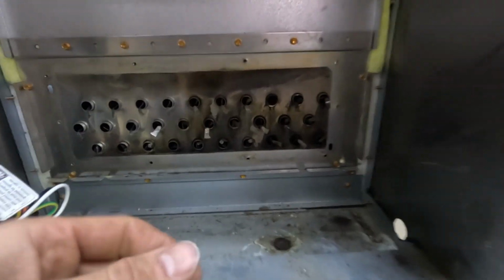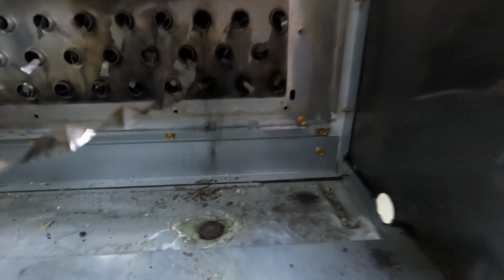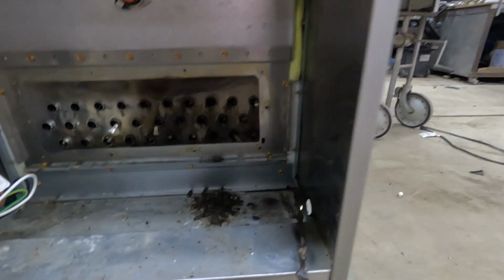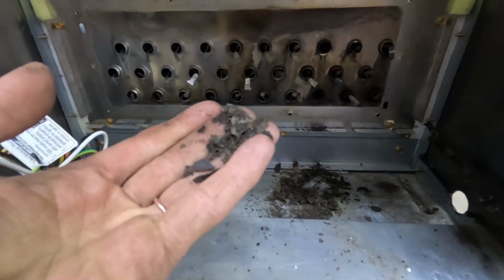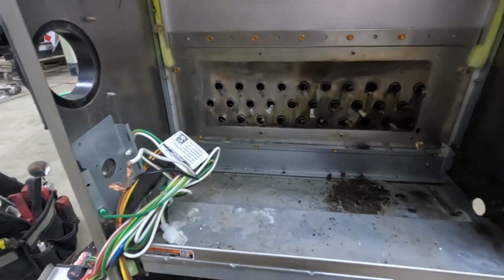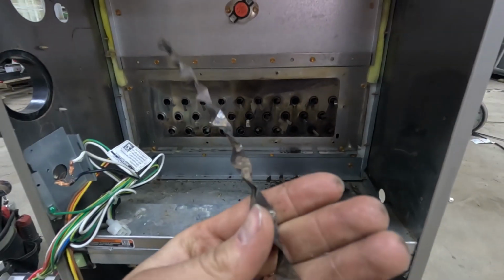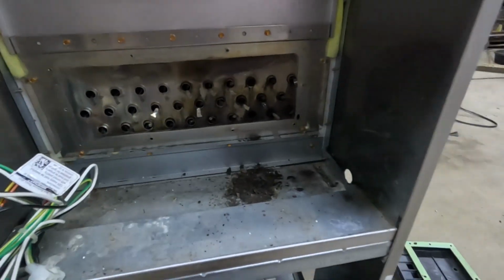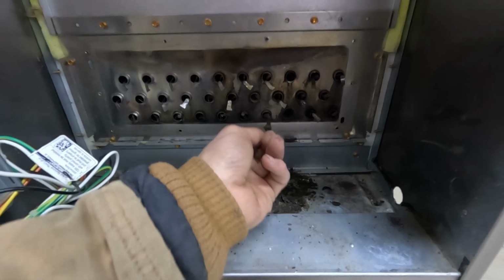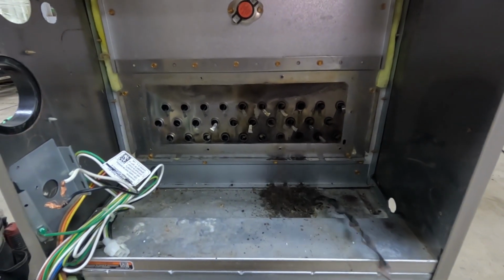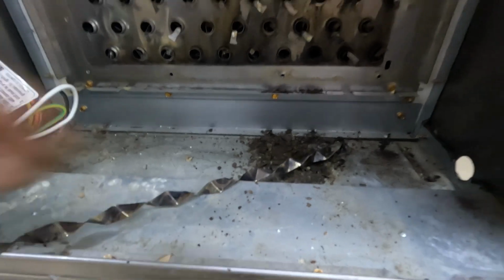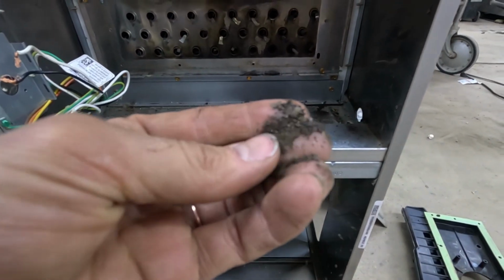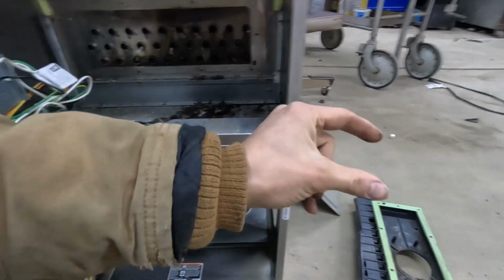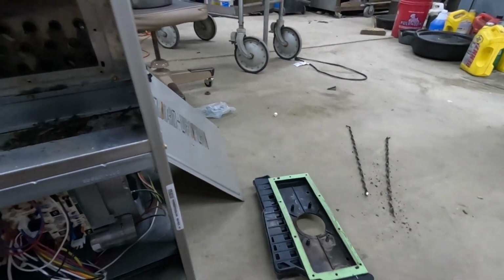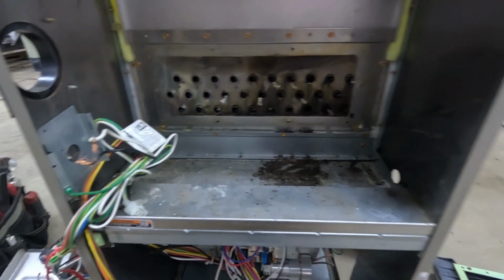There's our actual secondary heat exchanger. And you can see it does have a bunch of debris clogging it up. But it appears to be made out of a stainless steel, so I don't know why some sort of incomplete combustion still ate the heat exchanger. Look at that. Look how plugged up that is. Doesn't look like the old ones were plugged up with rust, but this just looks like dirt. It's kind of weird. In any case, we will proceed.